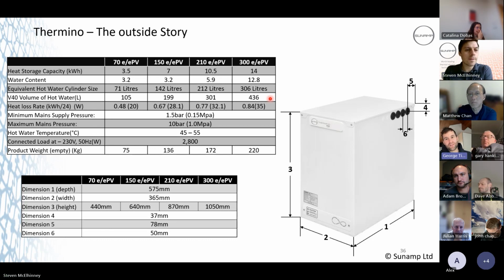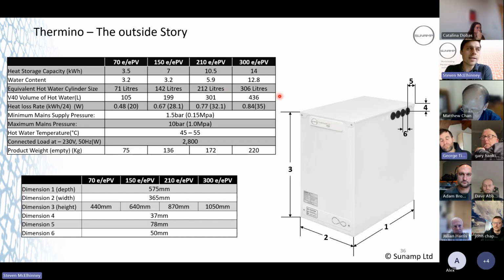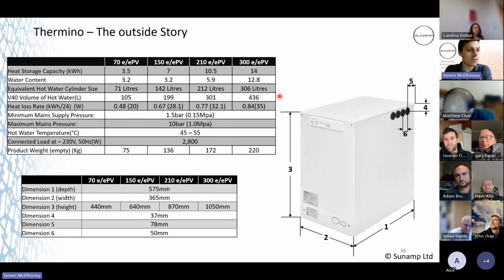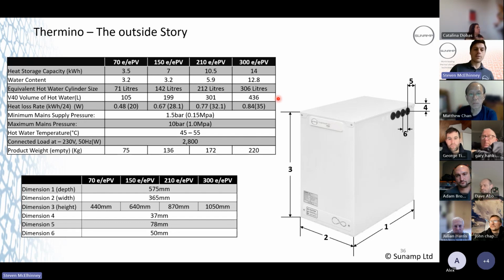You find you get issues occasionally, but do you publish those figures or is it just work it out, just use the maths? What's that, the figures of this? The figures obviously at different outlet temperatures. No, we don't. So again, the outlet temperatures can vary as well, obviously, with flow rates, if it's not being commissioned properly, and inlet water temperatures and stuff. So we tend just to stick to the 40. The 40 that the manufacturers go to, as you said. So hopefully it just gives you an idea of what the unit's capable of. Okay, George. I mean, again, as you said, if you've got a TMV set at 55, 55 is too hot for me.